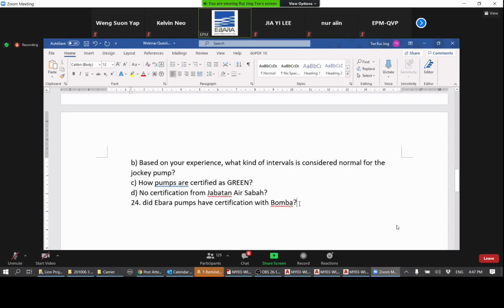Number 24, does the Ebara pump have certification with Bomba? Okay, good question. Bomba does not issue any form of certification. They do not say that this brand of pump is approved and that brand of sprinkler is approved. As far as we know, Bomba does not do that for any equipment. But the latest standard that has been issued requires compliance of fire pumps to the MS 2616 standard and ISO 9906. As long as your pump meets these two standards, Bomba should be approving it. All our pumps meet these two standards.